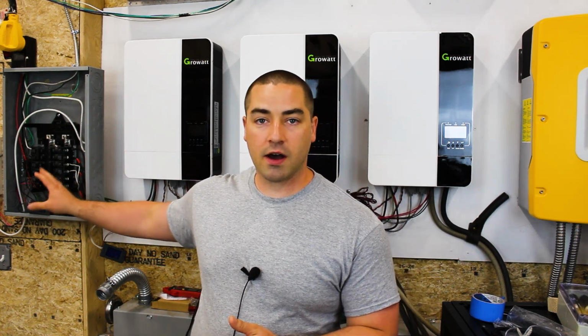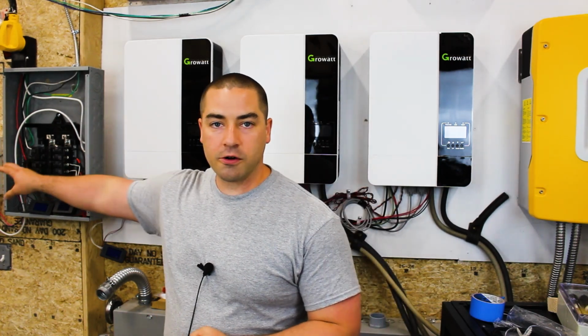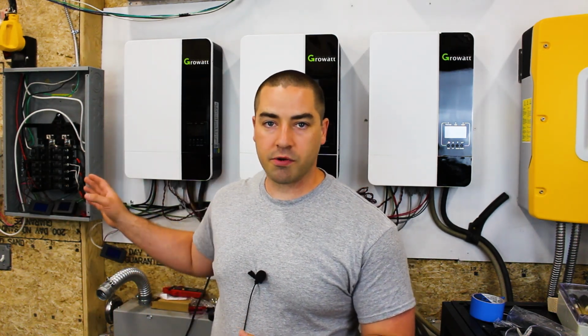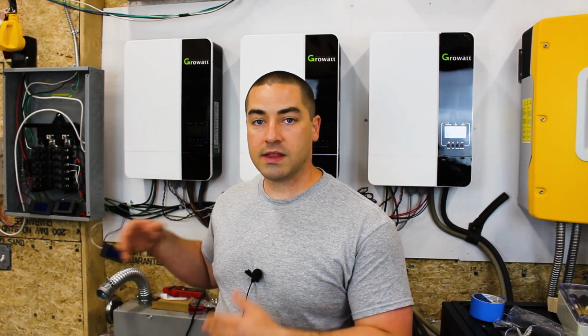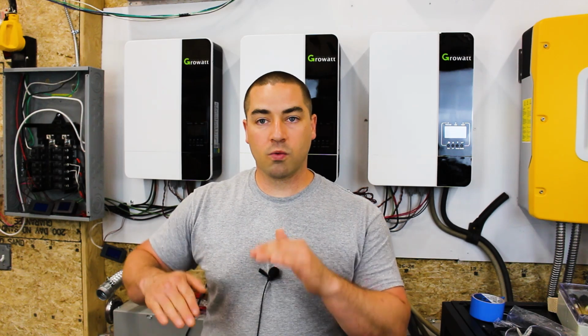Now, in a previous video, a lot of people commented that the way I wired up the auto transformer could potentially be a little dangerous. Basically, I have the auto transformer on its own circuit breaker. The potential problem is if that circuit breaker trips for any reason and the house and garage are still pulling power, there will be an imbalance somewhere between the two legs. The two legs have to add up to 240 volts because that's what they're putting out, but if you're not using much power on one and you are on the other, there will be an imbalance, a difference in voltage between the two sides.